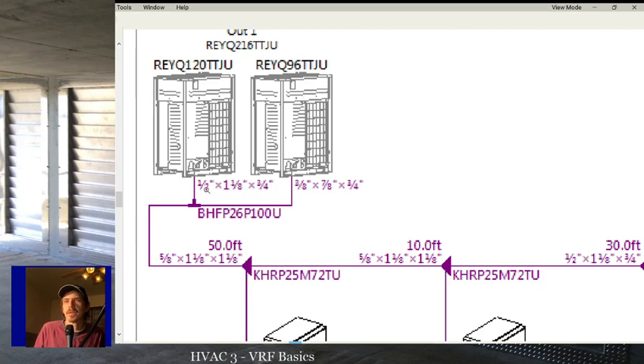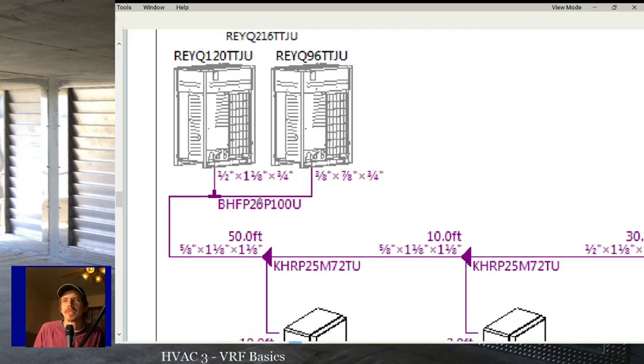This is liquid line, half inch, right? The inch and an eighth line would be the suction or the low pressure gas line, and then 3/4 would be the high pressure, low pressure gas line, or your discharge most of the time, or in times of high cooling it will turn into a second suction line. So again, with the three lines, you can always tell which one is which just by looking at the size, basically, because one will be the smallest, that'll be your liquid, biggest will be suction, and the other one will be high pressure, low pressure gas. Sometimes the high pressure, low pressure gas ends up the same size as the suction, but pretty rarely. Generally, they end up being different sizes.